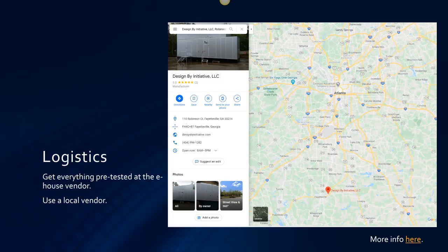This is an e-house manufacturer that I've familiarized myself with, and they're right here in Georgia, just south of Atlanta. And that pays dividends, because you can drive to the e-house manufacturer and watch the gear being tested if you like, watch the control system being tested, or witness the testing of the protective relays. And it's nice to be able to drive to those kinds of things versus having to fly. In addition, this particular e-house manufacturer has a unique design in which they're using an aluminum sheathing with some sort of core in it that has a very, very high R value, which reduces the HVAC load.